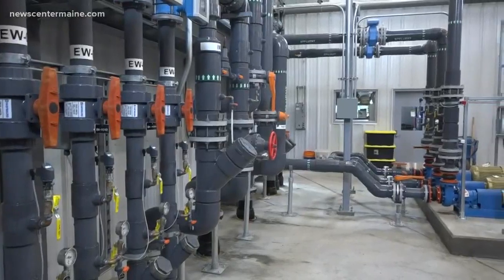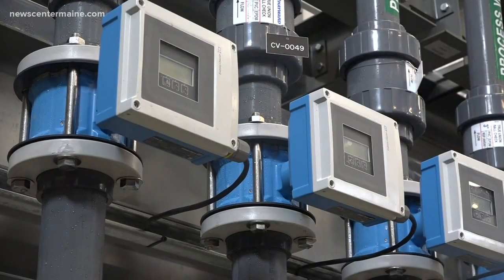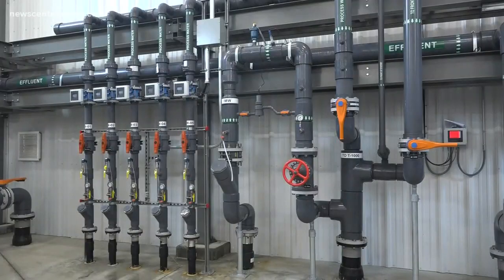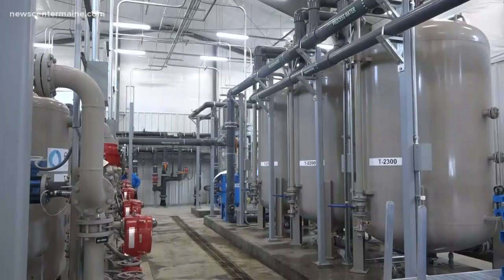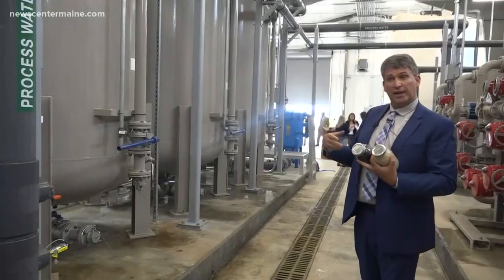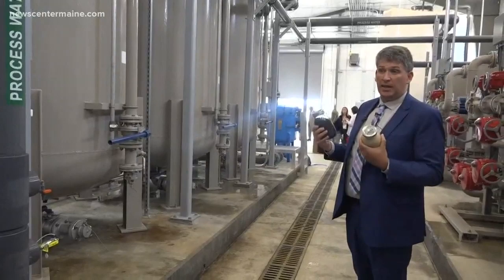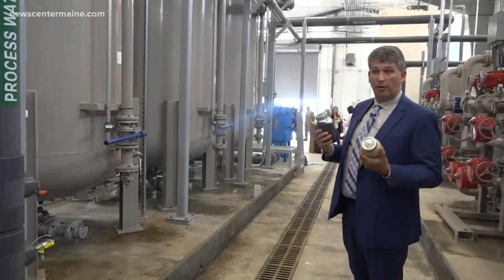Which is exactly what this groundwater treatment plant is aiming to do. The filtration system is connected to six different wells in the area. Water is collected and pumped through. Once it hits these granular carbon vessels, the magic really happens — it removes any organics that might be in the water, and also incidentally some of the PFAS and PFOA as well.